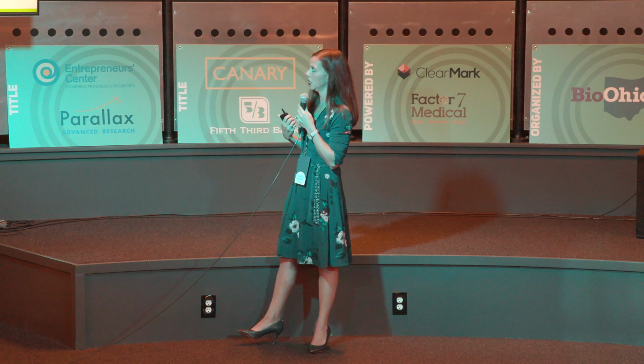And two of the main standards for quality management system requirements are 21 CFR 820 as well as ISO 13485. These probably sound very familiar to those in this industry, but the first one being FDA's regulations. So they're all of the regulations for good manufacturing practices for quality system requirements. It's the framework of what FDA wants to see when they come and do an audit or an investigation of your facility. It's all of the processes, the work instructions, the forms, pretty much everything that your company has to move forward with and have in place so that you can prove that you have the proper and appropriate controls from a quality perspective to be able to consistently create a product and get it to market for safe and effective use each and every time.